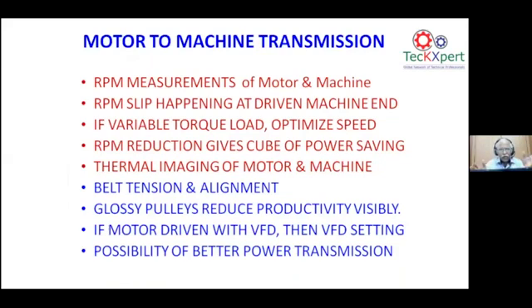So one is on the motor, the next one is on the motor to machine transmission. Take the RPM measurements from the motor to the machine, and see what slip is happening for the given motor and load. If it is a variable speed load, the speed has to be optimized, because again we go by the cube of this. Any RPM reduction gives a cube-of-the-speed power saving.